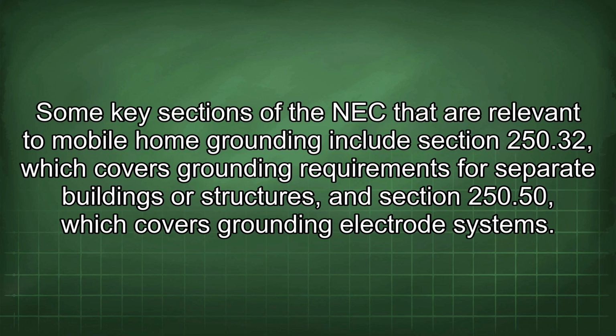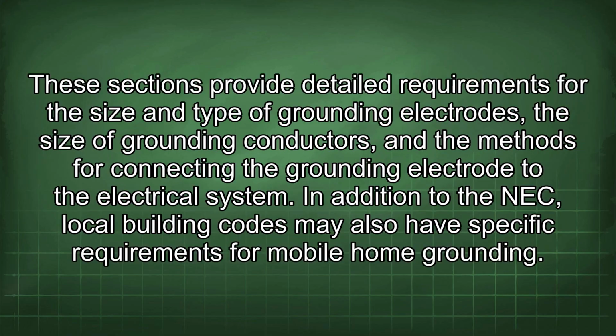Some key sections of the NEC that are relevant to mobile home grounding include Section 250.32, which covers grounding requirements for separate buildings or structures, and Section 250.50, which covers grounding electrode systems. These sections provide detailed requirements for the size and type of grounding electrodes, the size of grounding conductors, and the methods for connecting the grounding electrode to the electrical system.